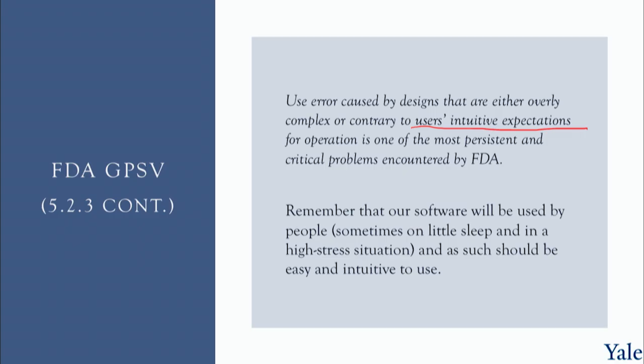Intuitive here doesn't necessarily mean intuitive from the perspective of the engineer. Intuitive may mean it should look like other software they use, and the button colors and the wording should match other tools that they use, because this will let them be intuitive. It should be easy to use because it looks like other things they have used. So a piece of software that is a radical redesign from what the users have used before may add much confusion and errors. And this is not an internet browser where they'll get used to it. In the process of getting used to it, real patients could suffer.